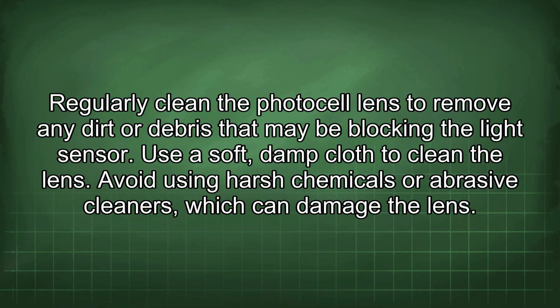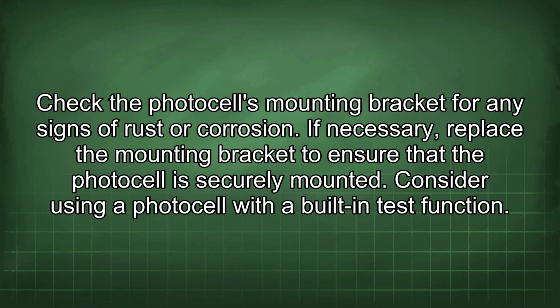Regularly clean the photocell lens to remove any dirt or debris that may be blocking the light sensor. Use a soft, damp cloth to clean the lens. Avoid using harsh chemicals or abrasive cleaners, which can damage the lens. Check the photocell's mounting bracket for any signs of rust or corrosion. If necessary, replace the mounting bracket to ensure that the photocell is securely mounted.